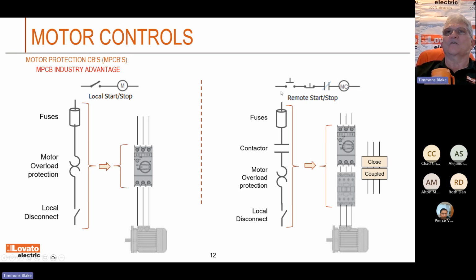Let's look at the right side over here. This uses a remote start stop, so naturally we're going to have to put a contactor in there to get some remote control on it. But where I would have before used a fuse, a contactor, a motor overload, and a disconnect, now I can just use a contactor and one of these motor protectors. And they can be close coupled. You don't have to wire between them. We have these little bridging things so you can close couple them. Big advantage in the panel building business using these things.